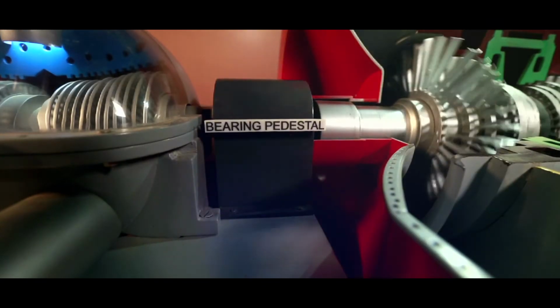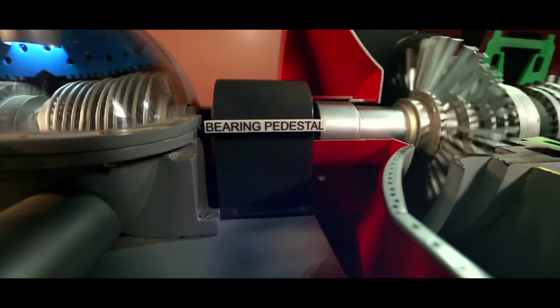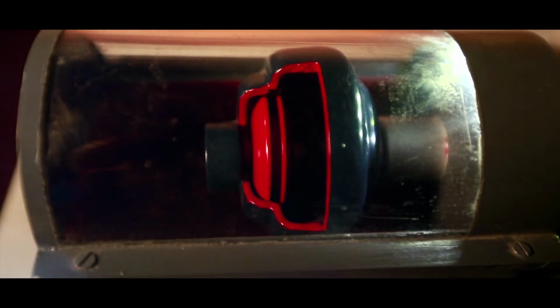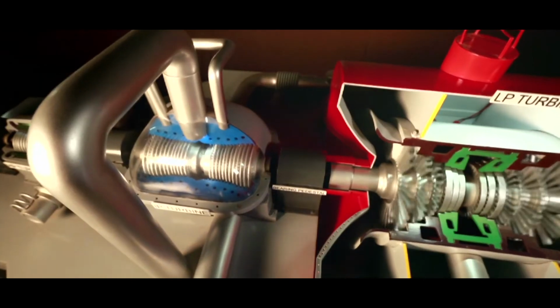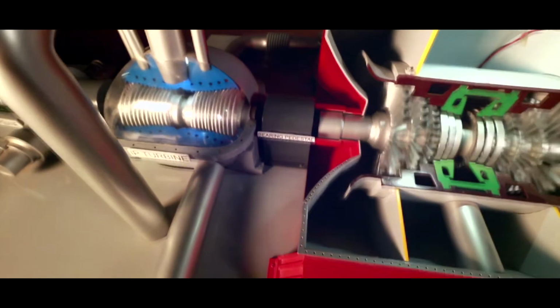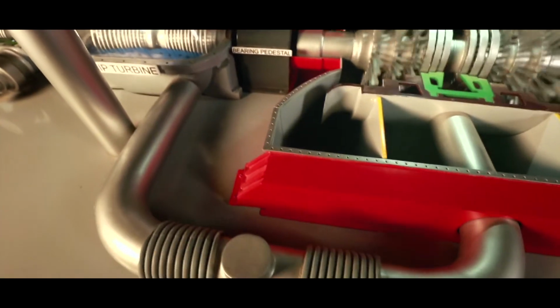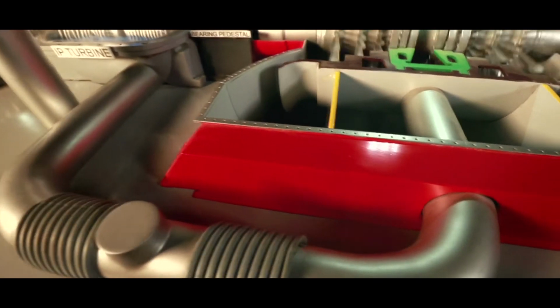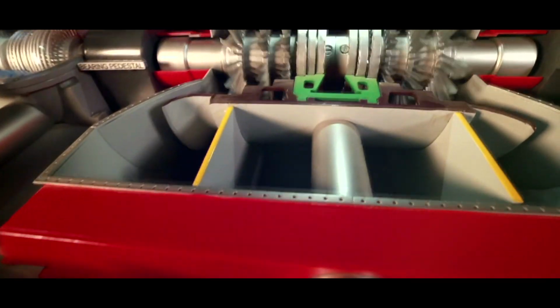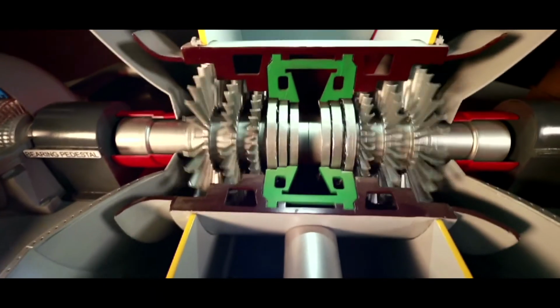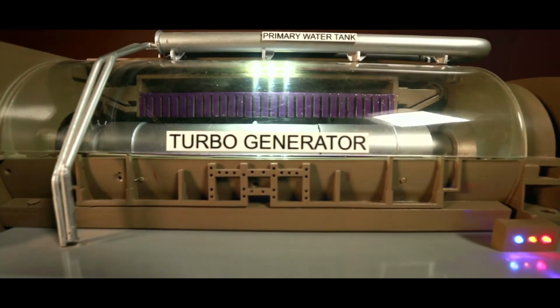This three-part construction is supported at various intervals by bearings, ensuring as frictionless rotation of the central shaft as possible. These journal bearings consist of an upper and lower shell. In order to prevent the bearing from exerting a bending pressure on the rotor, it is pivot mounted in a spherical support. This time-tested construction of the turbine ensures maximum efficiency and minimal breakdown time.